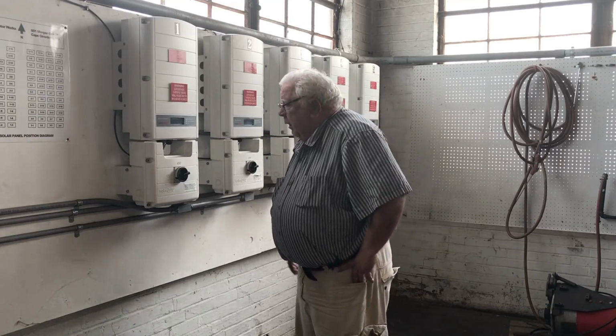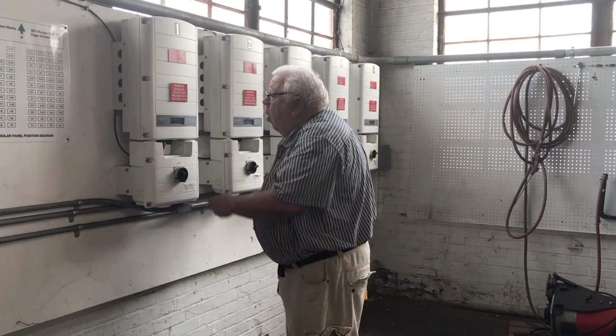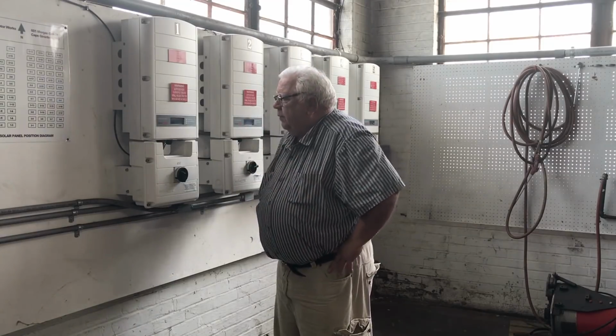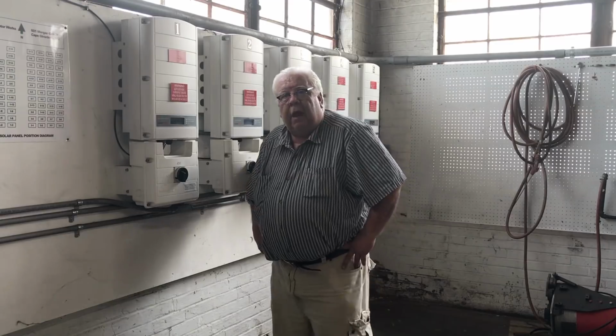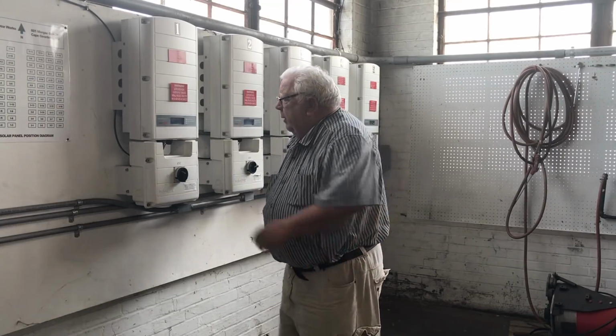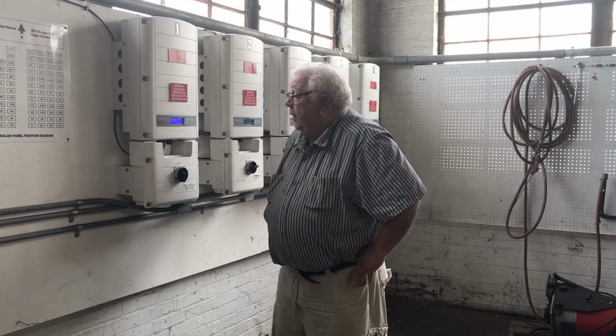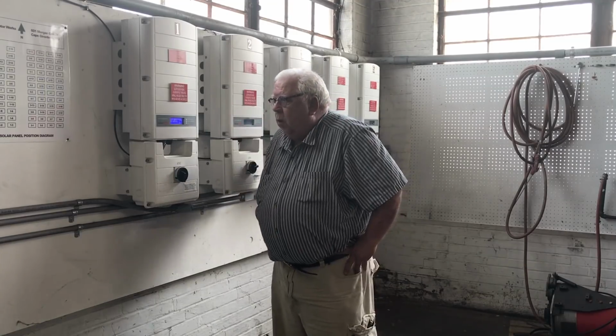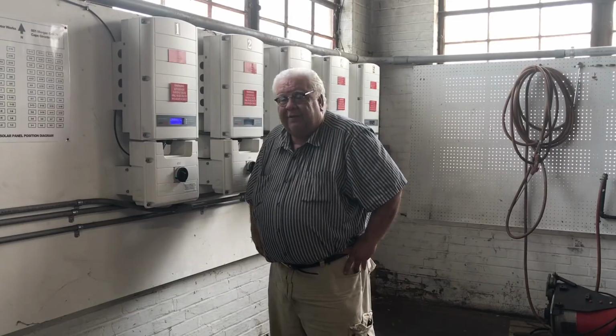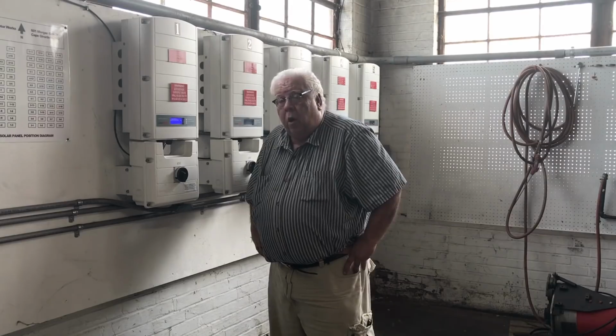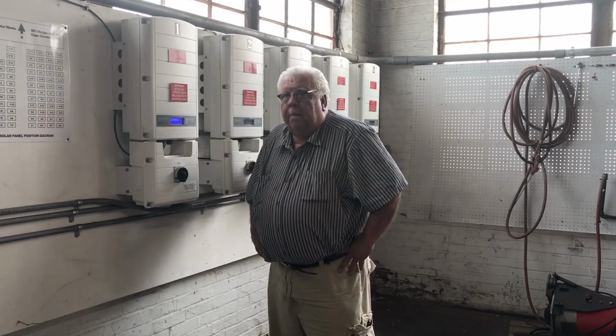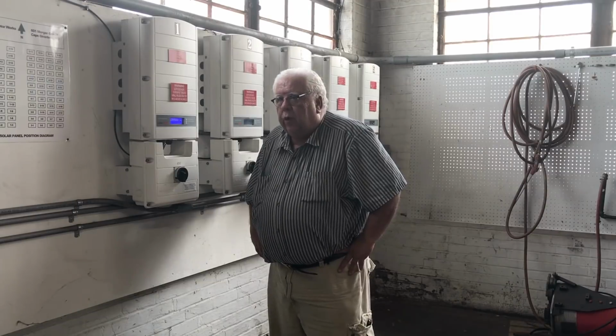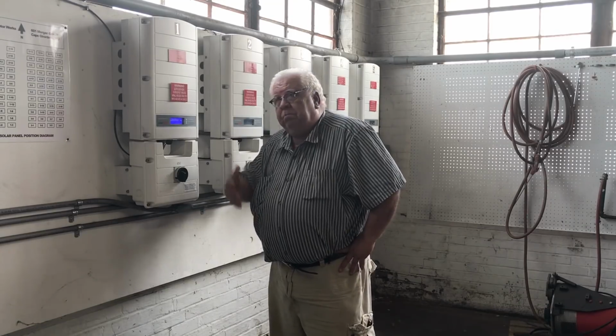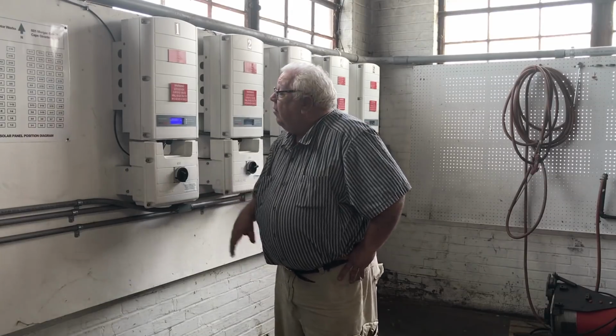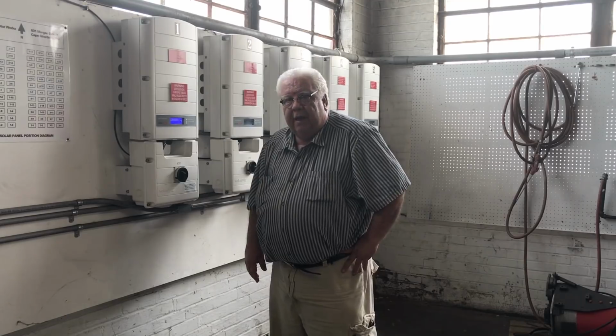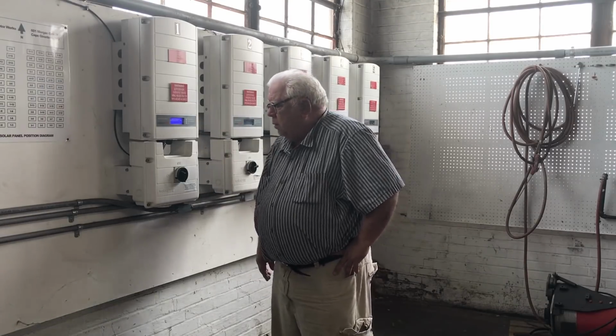And we're going to turn these on one at a time. Here's number 1. I set that to on, and it'll go through a power-up sequence. And then we'll have a 300-second delay, 5 minutes, while it comes up and does its connections to the internet, for one thing. It's a monitored system, and it also goes through a 300-second countdown, syncs to our 60 hertz waveform. We have the grid off and are using the 12 kilowatt low frequency transformer base 48 volt inverter as our grid, if you want. And this is going to sync to it, and we got 275 seconds left until this kicks in.